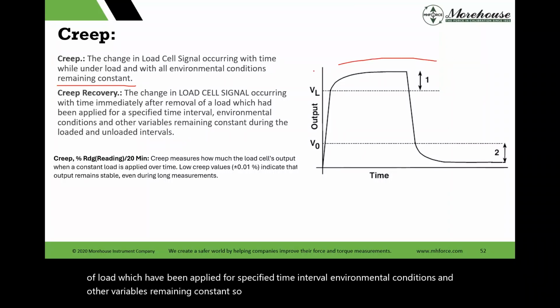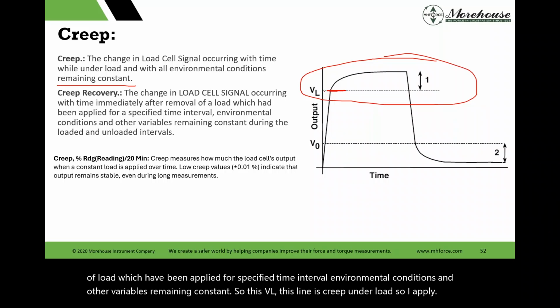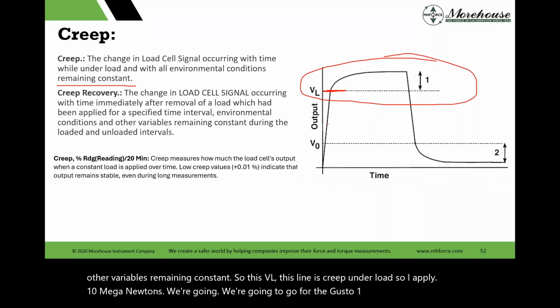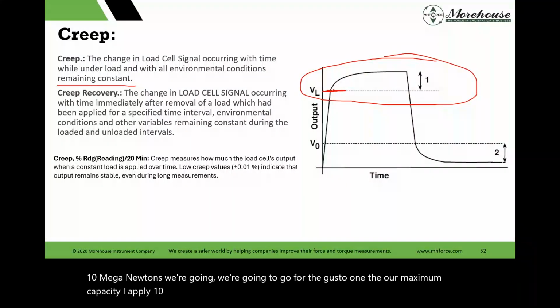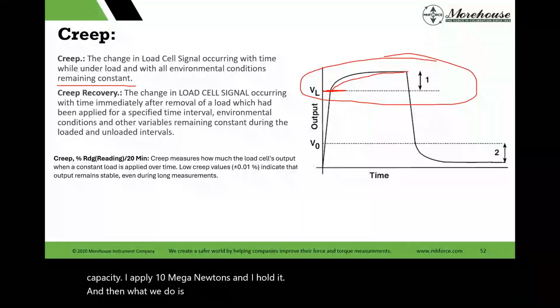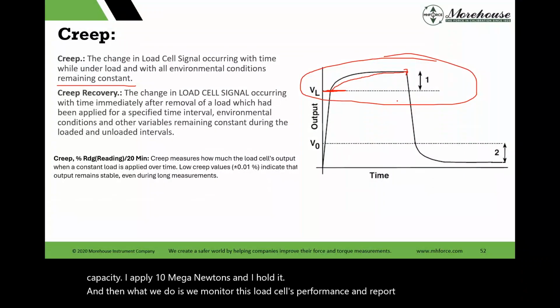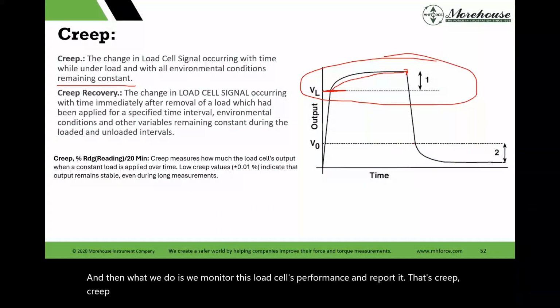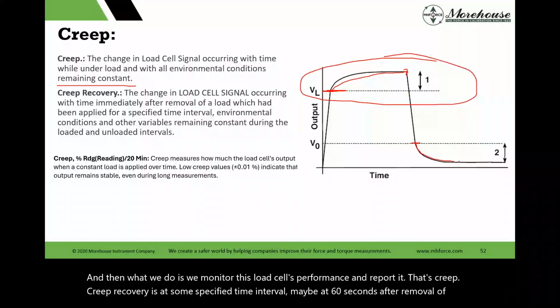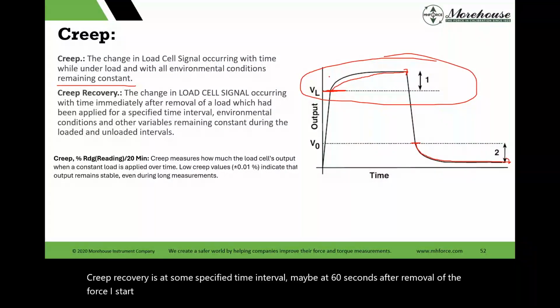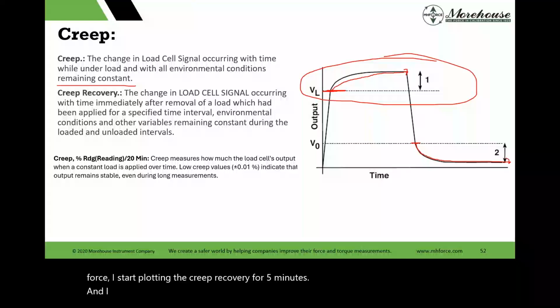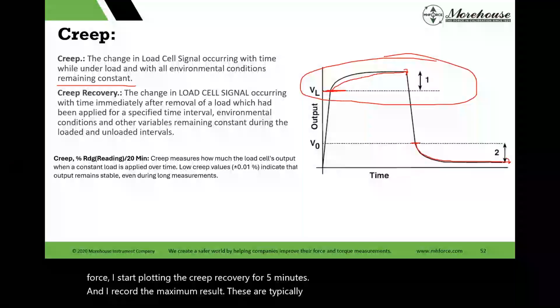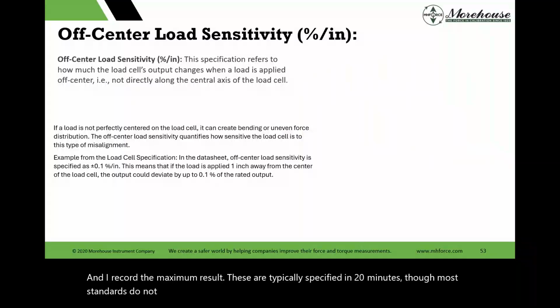So this line is creep under load. I apply 10 meganewtons. We're going to go for the gusto on our maximum capacity. I apply 10 meganewtons and I hold it. Then we monitor this load cell's performance and report it. That's creep. Creep recovery is at some specified time interval, maybe 60 seconds after removal of the force, and I start plotting the creep recovery for 5 minutes and record the maximum result. These are typically specified over 20 minutes, though most standards do not make us wait 20 minutes.